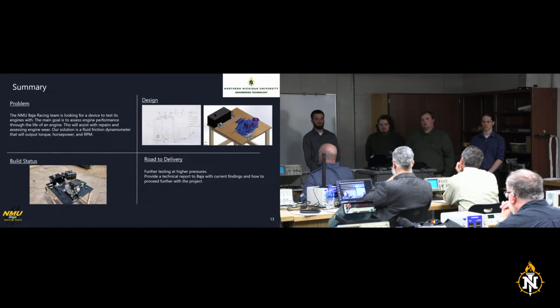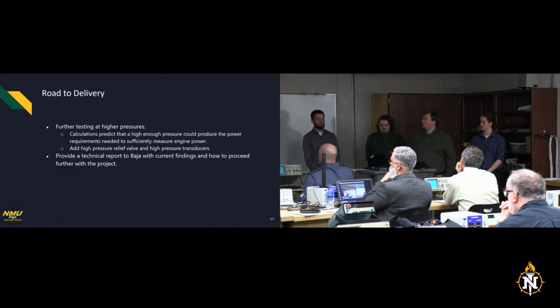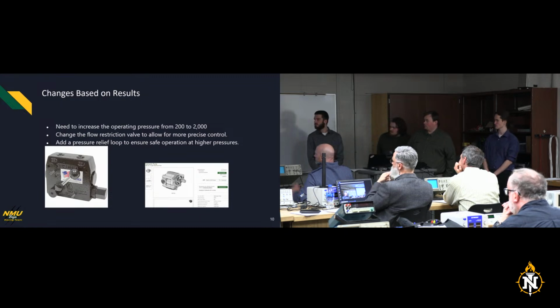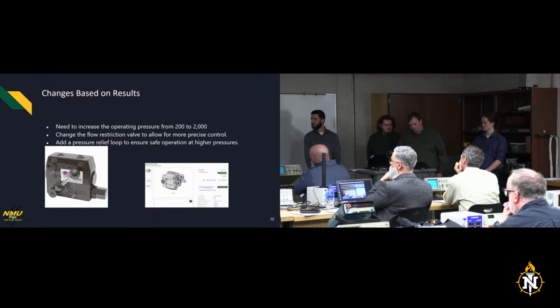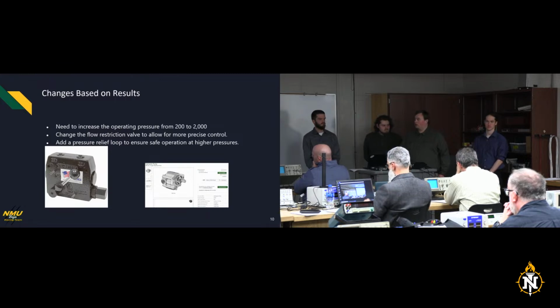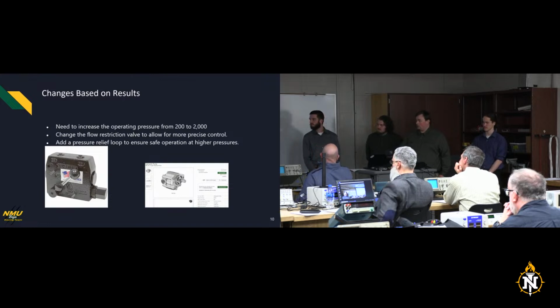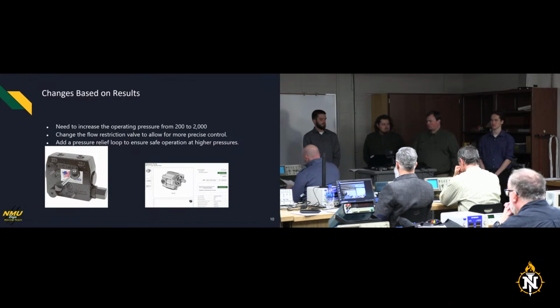So what components do we need to proceed? Right here is a combined flow restriction and pressure relief valve. That would be one of our main components, as well as a new pressure transducer. Our current high side pressure transducer only measures 500 psi. Its burst pressure is about 6,000, but it won't measure any more than 500, so we need to switch that for a 2,000 or 3,000 psi pressure transducer, as well as a couple of extra fluid fittings to integrate this pressure relief valve into the system properly, so we have an actual relief loop to feed back into the tank. Those would be the main components.